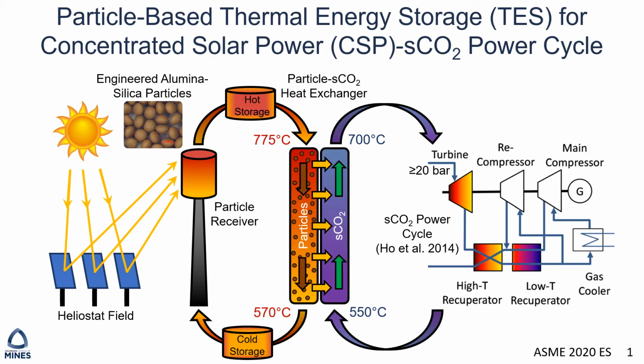Engineered alumina-silica particles are inexpensive, mechanically robust, chemically inert and non-corrosive, and offer a wide range of operating temperatures. On this slide, I show a schematic of a solar-driven SCO2 power plant with particle-based thermal energy storage. On the left, solar heat is stored in the particles as they pass to a particle receiver irradiated by concentrated sunlight at fluxes up to 1,000 suns.